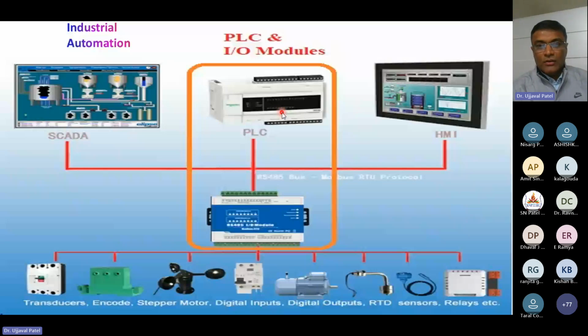At that time, we can turn on the AC. The output generated by the PLC for turning on the AC is applied to an output module. Some terminals of this input-output module work as digital inputs, and some work as digital outputs. The digital output generated from the PLC is applied to the output module, and from there to a relay.